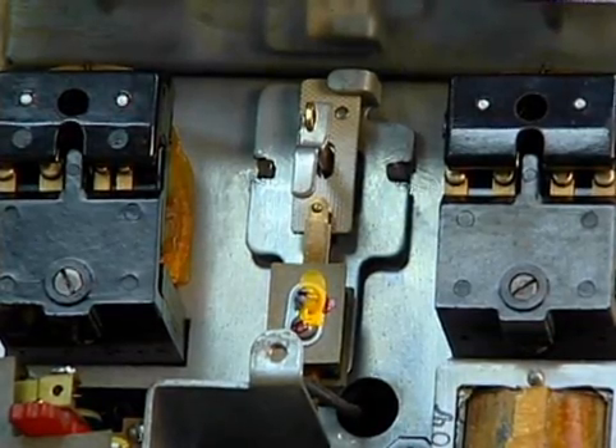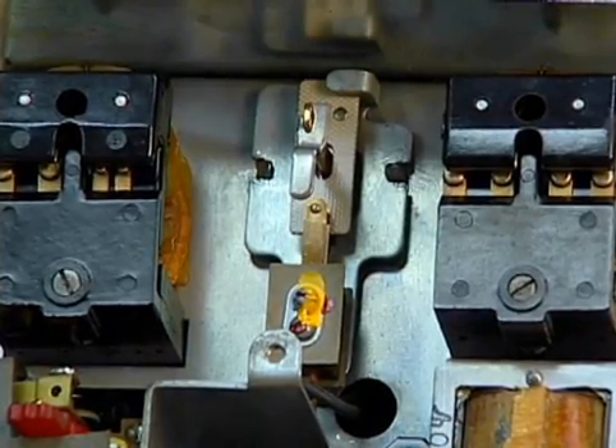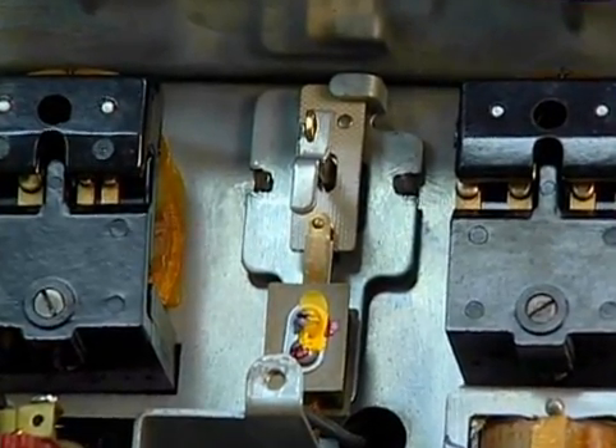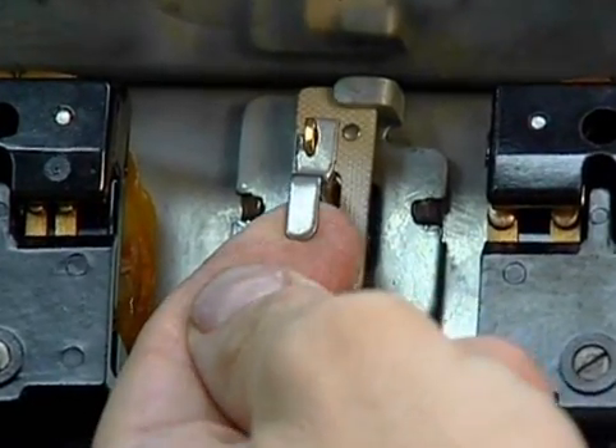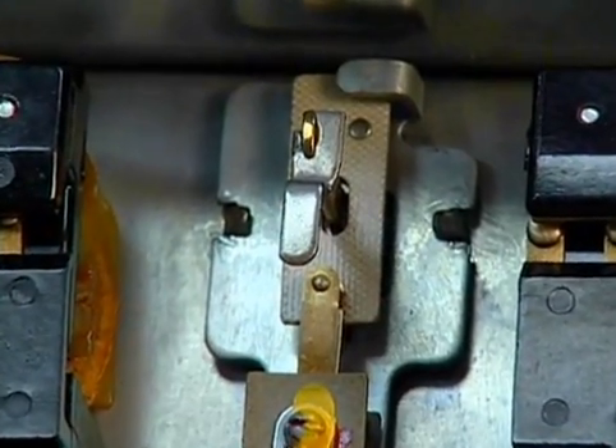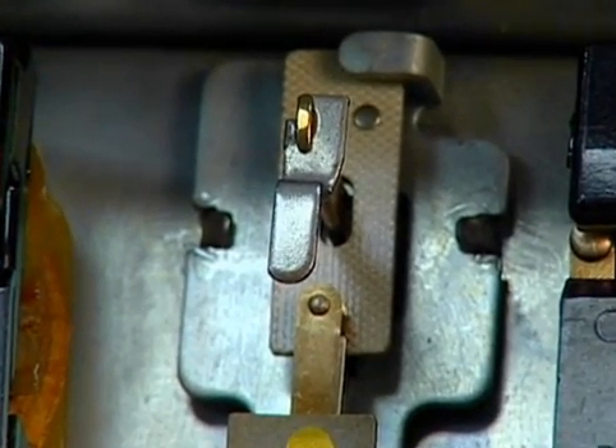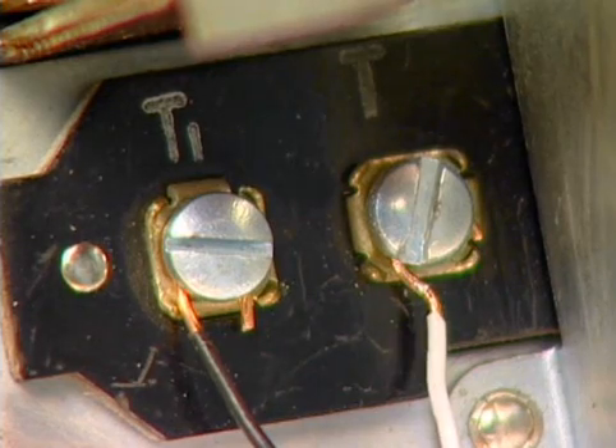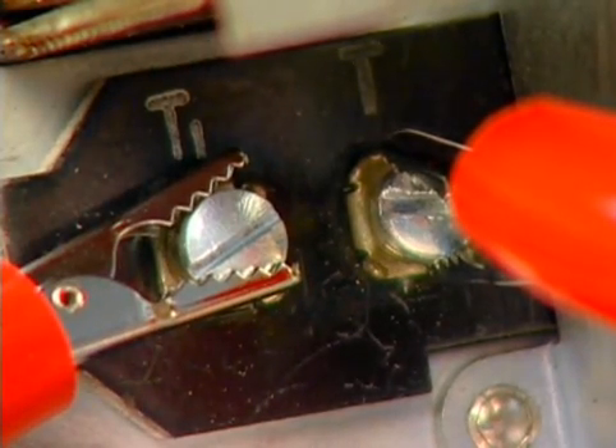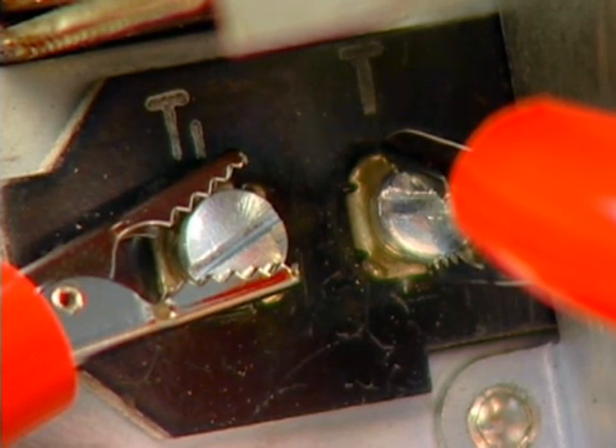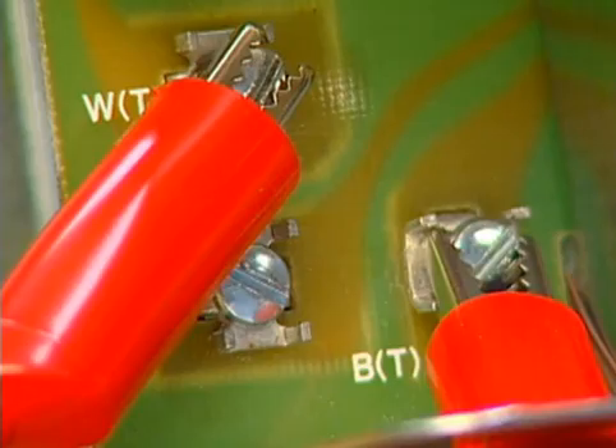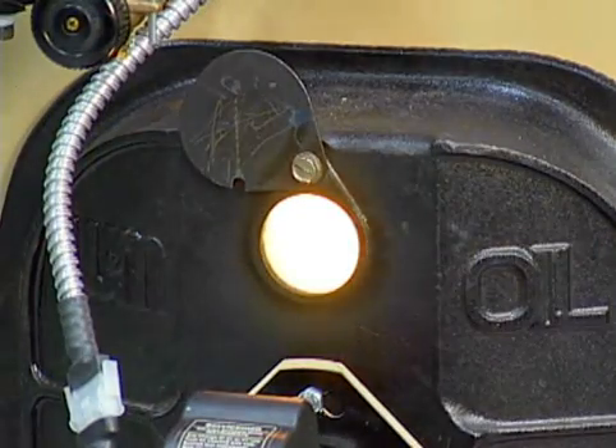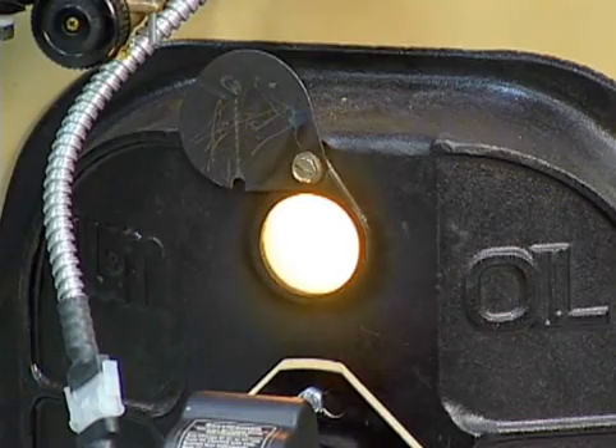If there is sufficient voltage, verify that the unit is in step, meaning that the contacts affected by the bimetal heat sensing element are properly aligned. This control is put in step by pulling the drive shaft lever forward 1/4 inch and slowly releasing it. If the primary still doesn't operate, the problem may be in the low voltage circuit. After removing all low voltage wiring from the control to avoid harming today's computerized thermostats, place a jumper across the thermostat terminals, either the TT terminals or the W and B terminals. If the primary control then starts the burner, the problem is in the low voltage circuit.